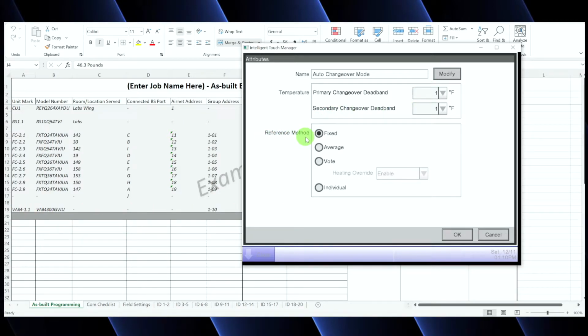Regarding the reference method, you're going to have this set to individual anytime you have a heat recovery system. And that's because we want each indoor unit to have an individual reference. We don't want 102 to switch over when 101 switches over. The only time you're going to change the reference method to fixed, average, or voting is when you have a heat pump system, or maybe you have a group of indoor units that share one port on a heat recovery system.